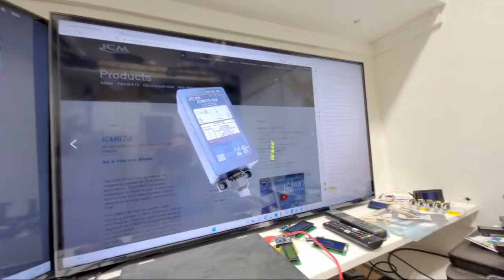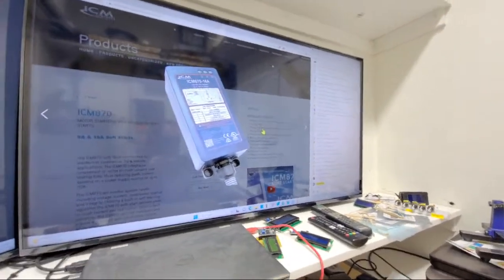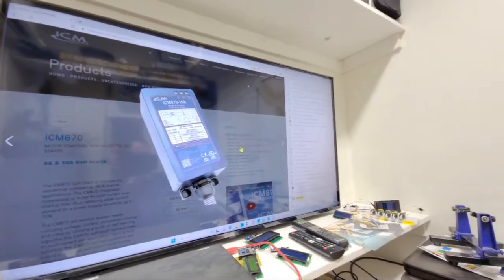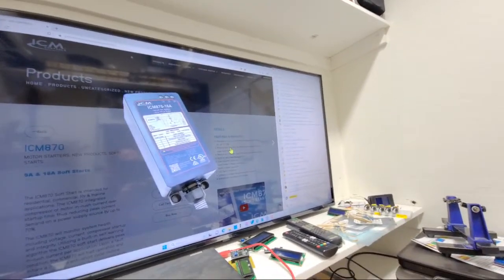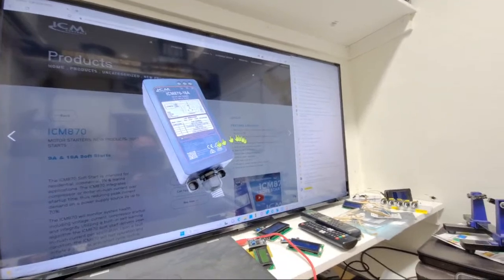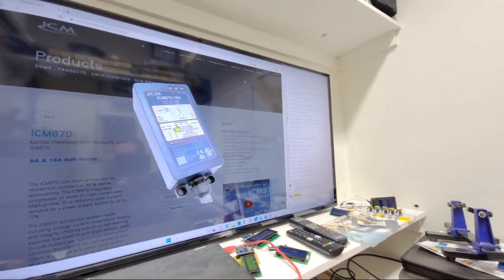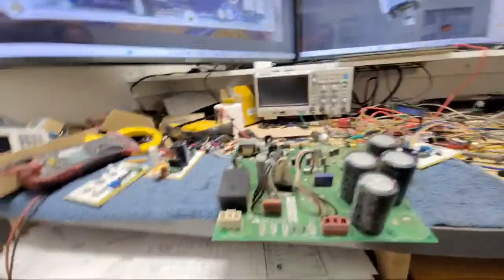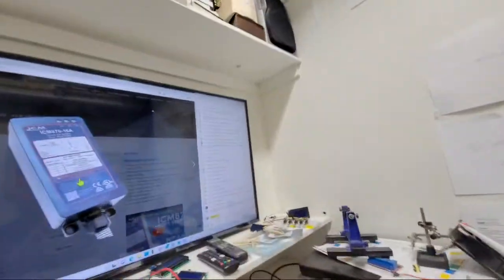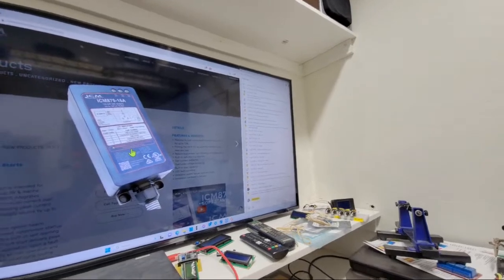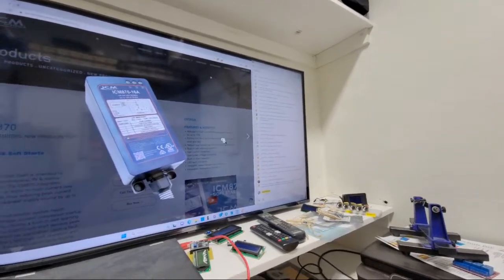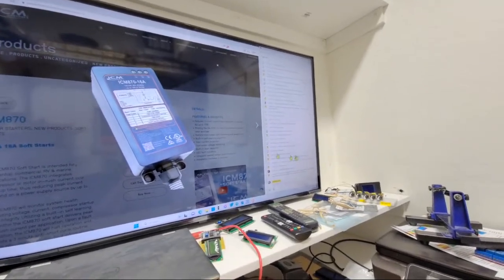So real soft starts are variable frequency start, and then they transfer over once they get up to speed. It can just be a low-spec variable frequency drive, because it just needs to get the compressor or motor going from a dead stop. It gives up the frequency for a couple seconds, and then a transfer switch bypasses it, and it's in bypass mode until the next start.